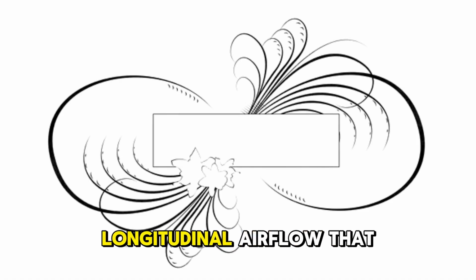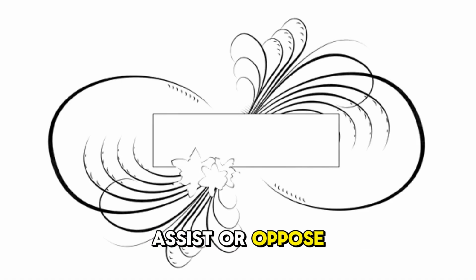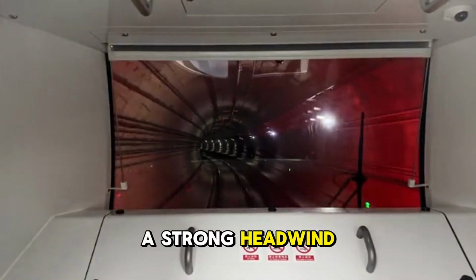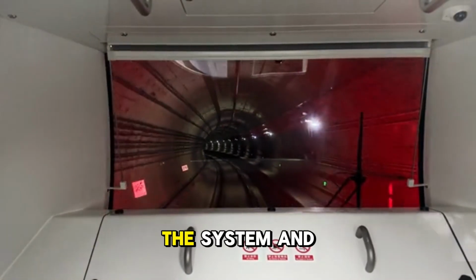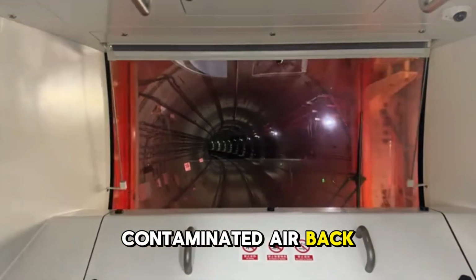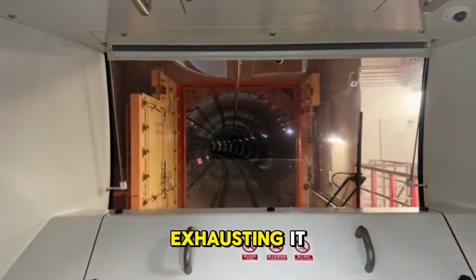Wind blowing into one portal creates a natural longitudinal airflow that may assist or oppose the mechanical system. A strong headwind at the entry portal can overwhelm the system and push contaminated air back into the tunnel rather than exhausting it.